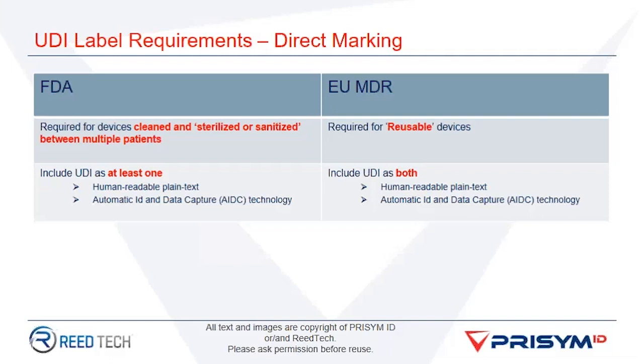There's a question here about what about NHS requirements for the UK? Are they consistent with EU MDR? Yes, so there are some timelines in place. Some of those milestones have already transpired for your Class 3 products, and Class 2A and 2B later this year.